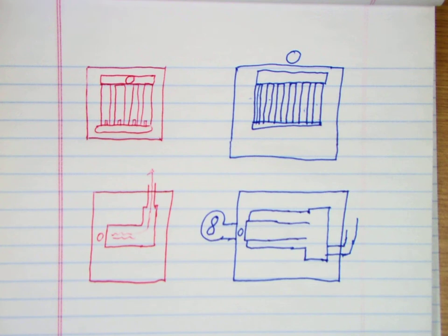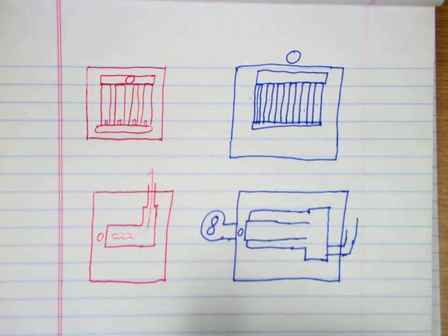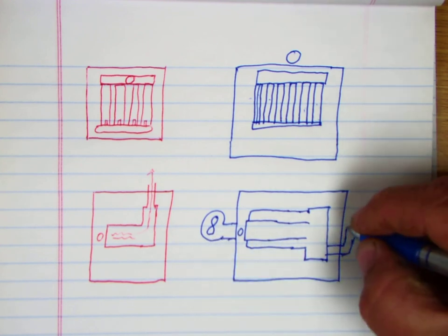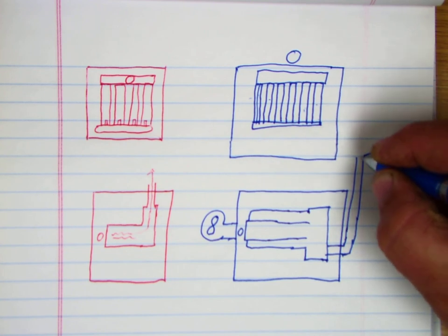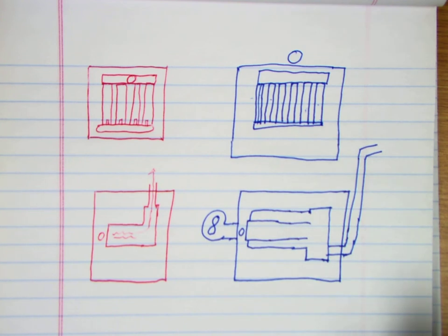We're just giving more area for the air that the fan is blowing through to absorb that heat. You look at them from the side. This one, like I say, was natural convection. These were lit with a pilot light. The mid efficiency furnaces and the high efficiency furnaces both use a combustion fan, which, as in the other video, is going to purge the gas out of here. It's going to prove that there is an airway through the combustion chamber, through the flue, and outside.